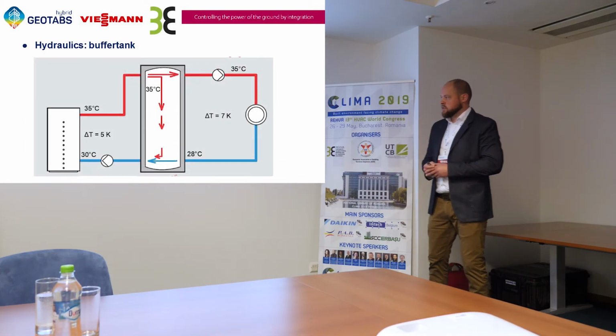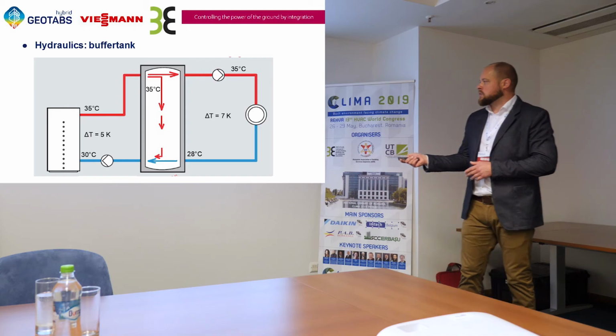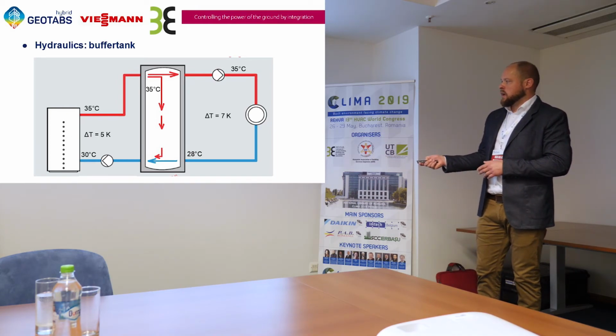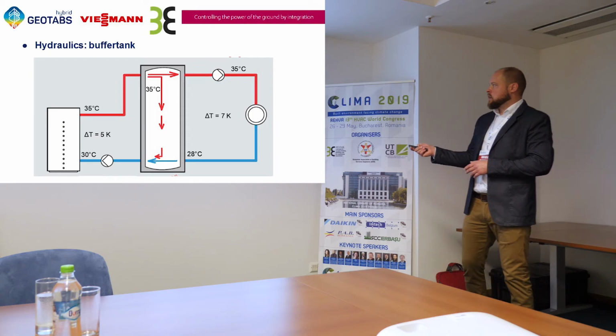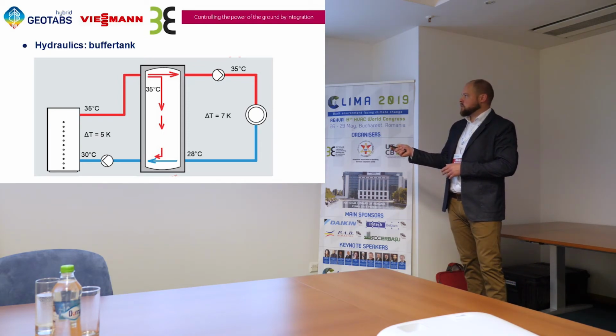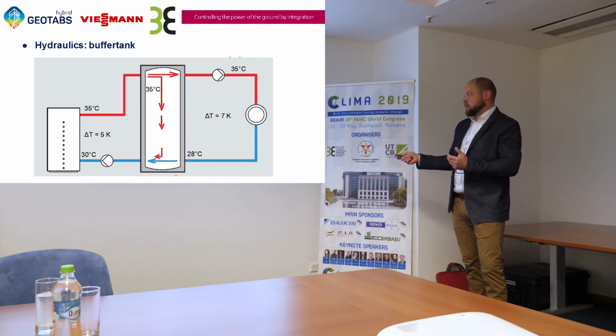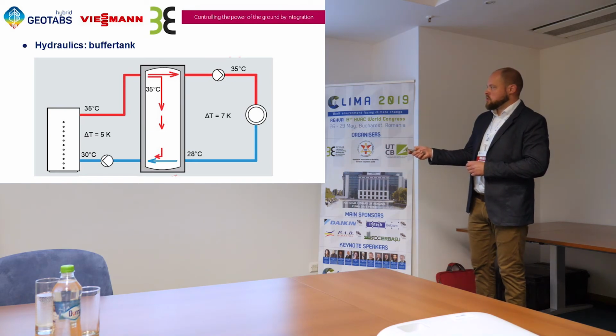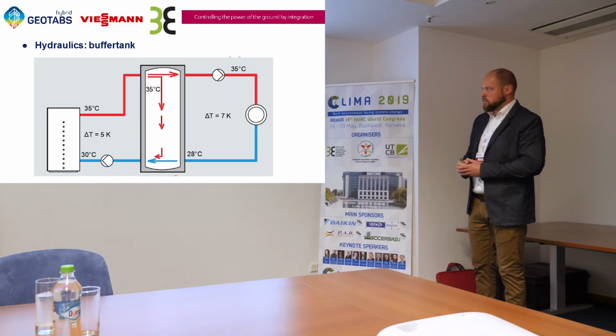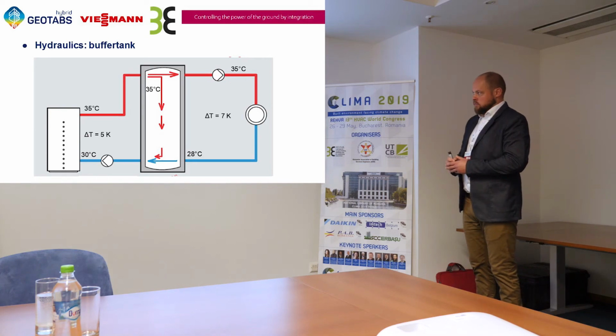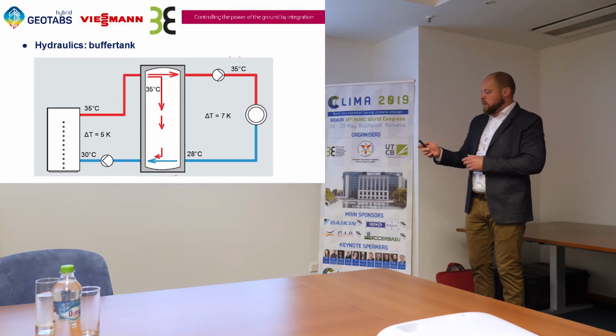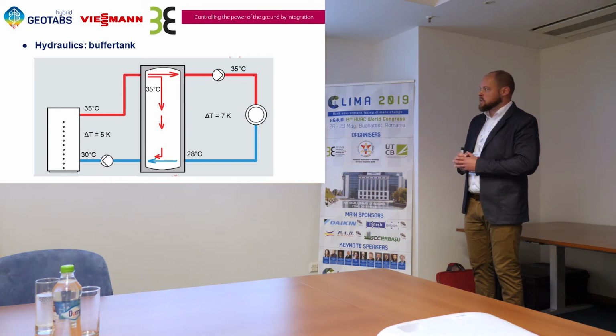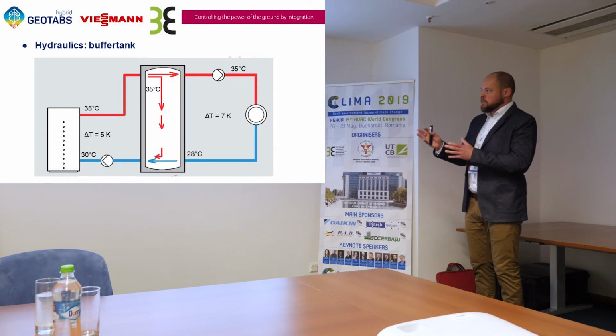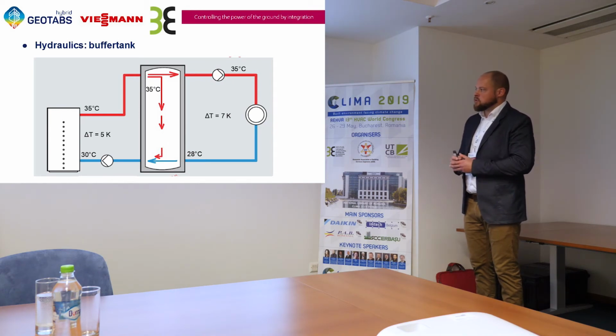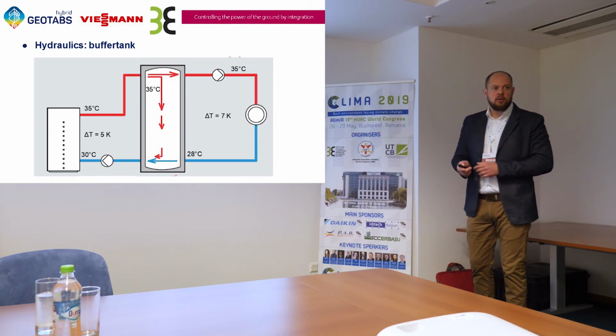Here you can see different delta T's we use. So I spoke about the delta T of 5 Kelvin on this side. So we have 30 return, 35 in the buffer tank. Through the installation we have a departing temperature of 35 degrees, but here we work with a higher delta T, so a lower flow on this side. And we see that we charge the buffer tank when it is full, the compressor will stop. So we need this buffer tank to get a separation between the two pumps. This pump and this pump have to be hydraulically separated, and we use the buffer tank in this case, because of the different delta T's we use, for a minimum running time of the heat pump.